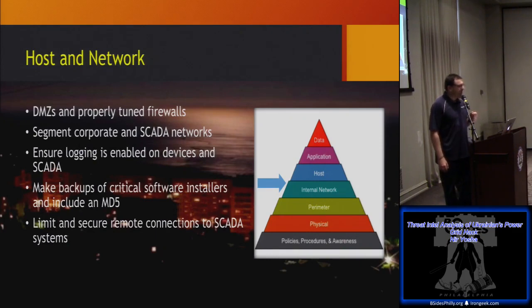From an architecture perspective, I believe air gap is something that should be considered for those sensitive operation networks. If not, add a DMZ and add a higher level. Obviously, the VPN was not secure enough in that specific incident, so make sure you have extra layers of security over the VPN. And again, I can tell you from experience that most of the vendors will ask you for a VPN to support the equipment. People from Honeywell or Yokogawa or any of the process automation providers want to be able to support it, and the users want to be able to get some support from their vendors. But as a network security guy, you want to make sure that there are a few levels of multi-factor authentication and other security measures.